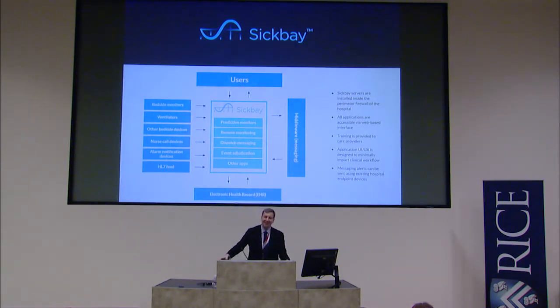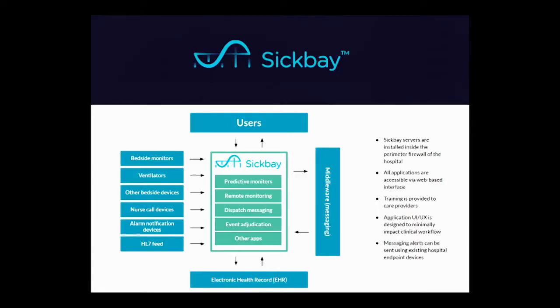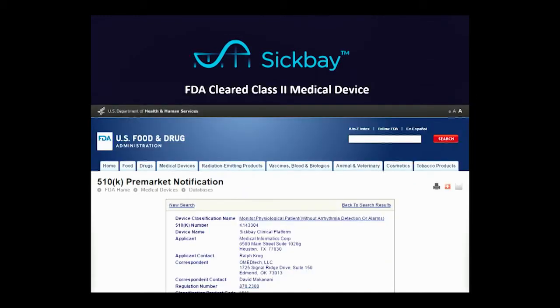We're very proud that we got the FDA to recognize Sickbay as a Class 2 medical device. What Sickbay does is take all the data from bedside monitors, ventilators, near-infrared devices, pumps, nurse call, alarm notifications, and anything that goes in and out of an EMR. It processes all that information in real time to provide new and useful metrics to users like physicians, to middleware systems, and to the EMR. It kind of acts like the CPU of a hospital.